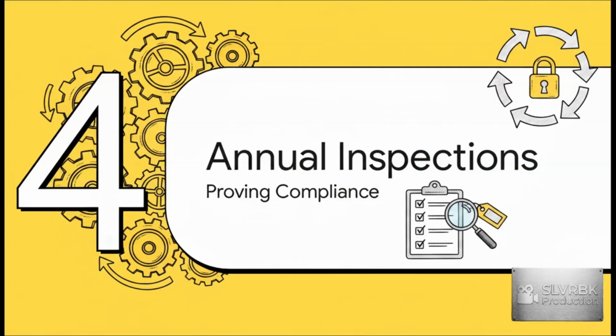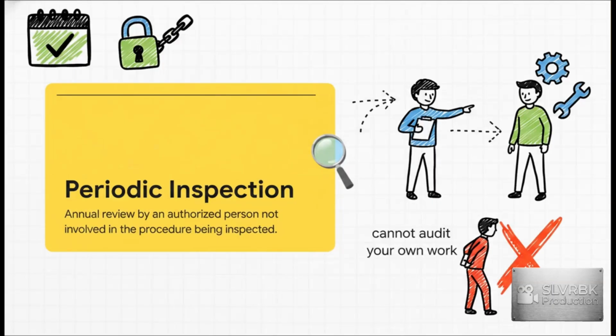Let's talk about holding ourselves accountable. You might have a great program on paper, but OSHA requires you to prove it's working by doing a periodic inspection at least once a year. The most crucial rule here? You can't grade your own homework. The inspector has to be an authorized person who is completely independent of the procedure they're evaluating. They need to physically watch the workers do the lockout and verify no one is taking shortcuts.